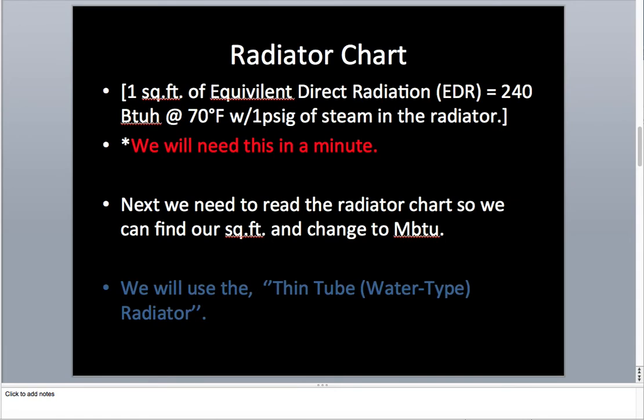So we're going to look at the radiator chart. One thing you're going to realize is one square foot of equivalent direct radiation, EDR, equals 240 BTU British thermal units per hour at 70 degrees with one PSIG of steam in the radiator. We'll need to know this in a minute. You don't have to remember everything verbatim, but we're just going over this real quick.